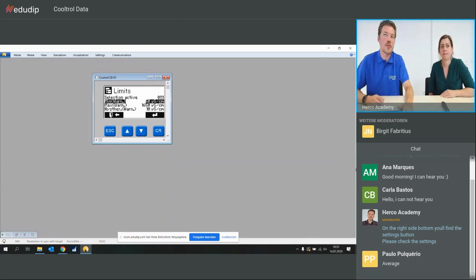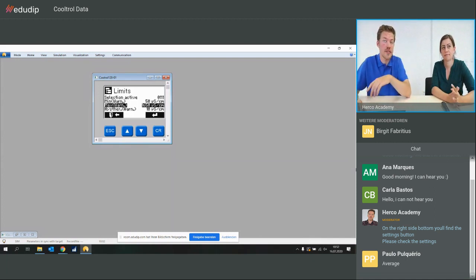So you see, min warning is like 50 microsiemens. This can't happen normally with normal tap water with like 500 microsiemens. And then also the max warning. We have to differentiate this. There's a warning and then an alarm. And we can also say, okay, what we want to do. Do we want to continue to operate the system or do we want to stop it? This is always depending on the application afterwards.